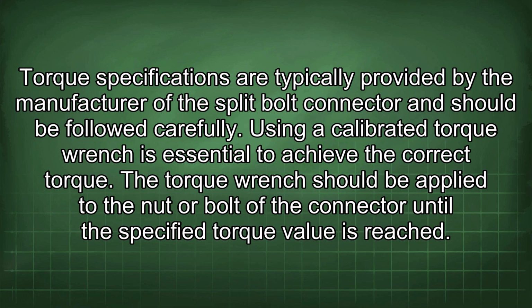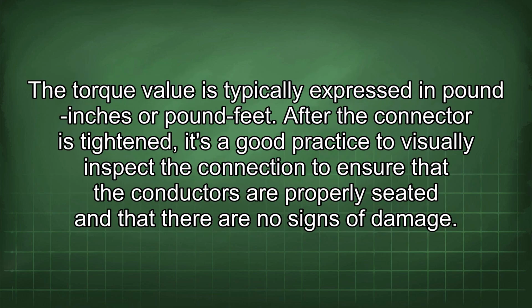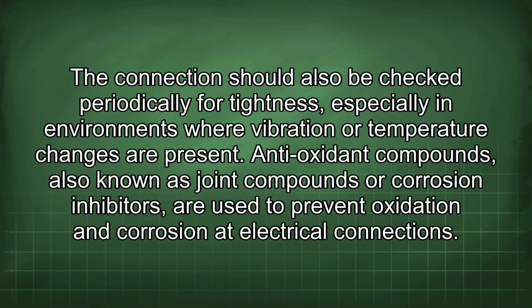The torque wrench should be applied to the nut or bolt of the connector until the specified torque value is reached. The torque value is typically expressed in pound-inches or pound-feet. After the connector is tightened, it's a good practice to visually inspect the connection to ensure that the conductors are properly seated and that there are no signs of damage. The connection should also be checked periodically for tightness, especially in environments where vibration or temperature changes are present.